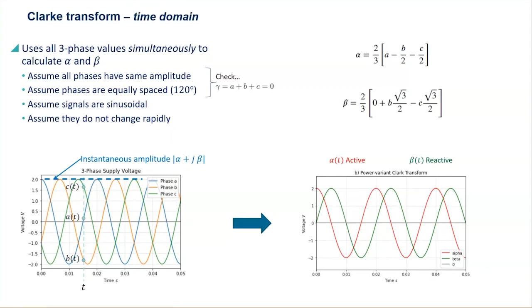So alpha, we can find using this really simple equation: if I take the value at A minus half the value at B minus half the value at C, multiply it by 2/3, that tells me the value of alpha at that time. And beta follows this one. And if I want to find out the instantaneous amplitude, all I have to do is take the modulus of alpha and beta. And if you look, you can see that even though these sine waves are going up and down like sine waves do, what this is doing is showing us where the envelope of those are. So at any point in time, I can tell you what the amplitude really is. I don't have to wait until I get a peak. And it can be changing in real time too. So even in this, where we've got this little peak coming out, which is a fraction of a second, we can pick that up using these instantaneous methods. We wouldn't pick that up if we had to wait for a half cycle to evolve.